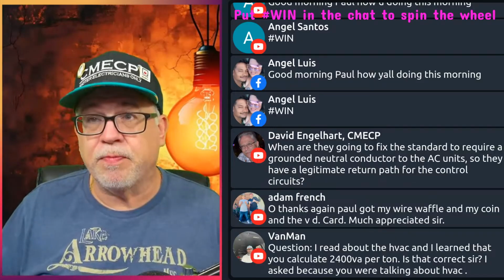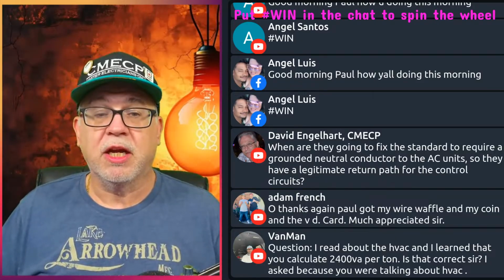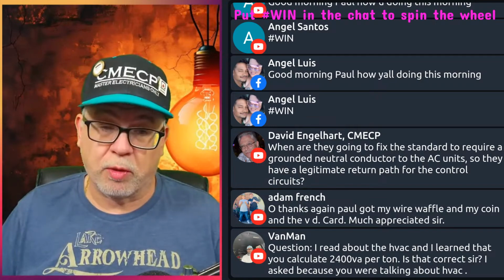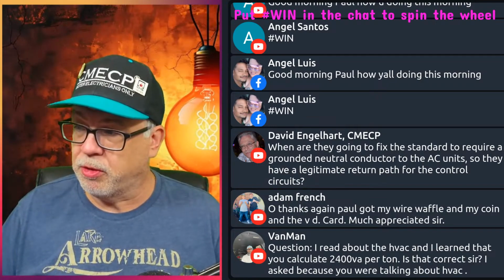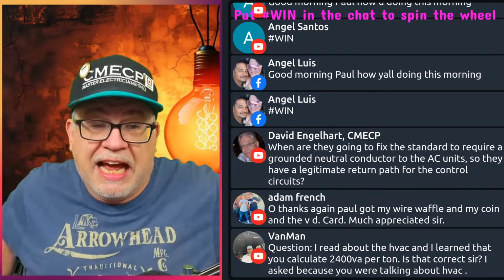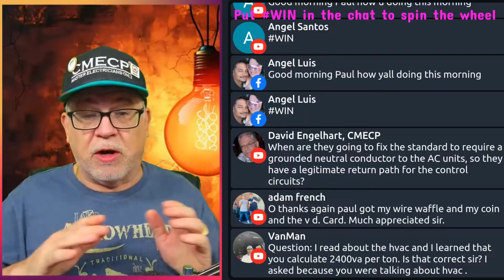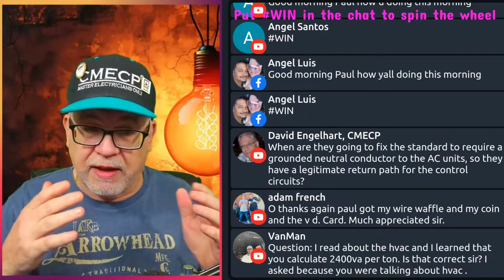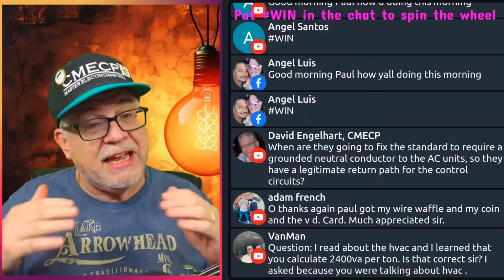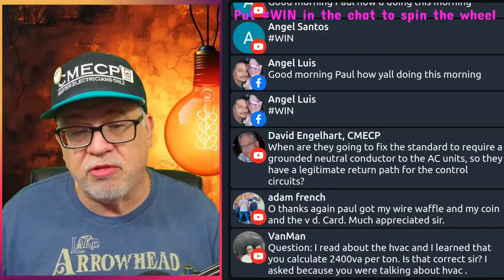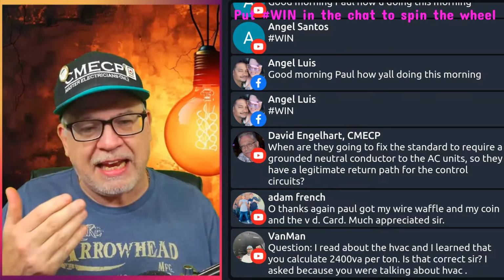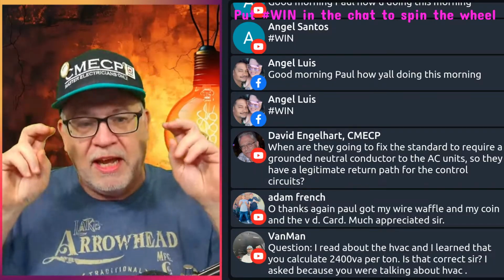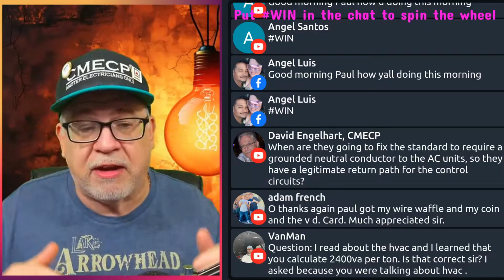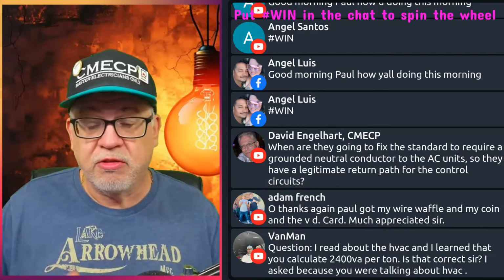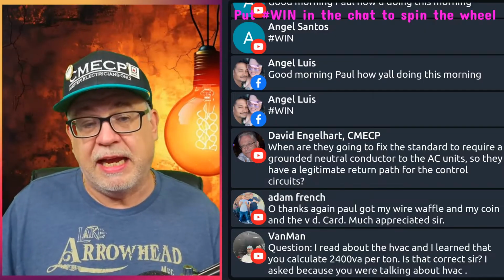And I think that it could be a problem come September 1st, 2026, when people are going to have to start using the GFCIs. Now, they did give an option for a Class C GFCI, SP, special purpose, but again, that's a higher milliamp threshold. Is it really providing the personnel protection? Manufacturers, obviously they pushed for it, so they're the ones that are going to have to answer to that.